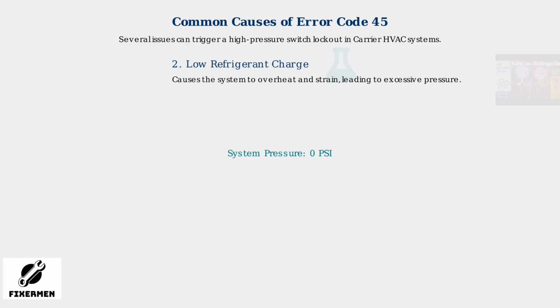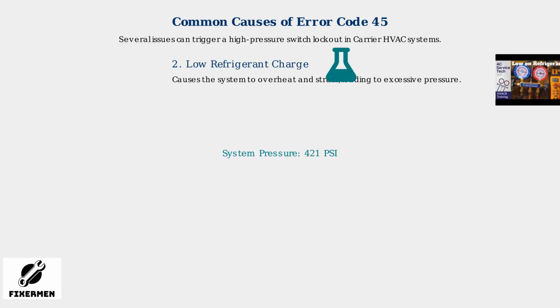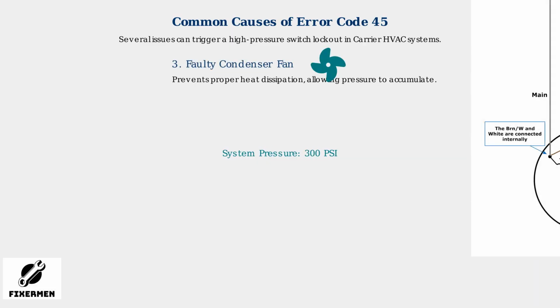The second cause is a low refrigerant charge. When refrigerant levels drop too low, the system cannot cool properly. This causes the compressor and other components to overheat and strain, rapidly building up pressure in the system. The third cause is a faulty condenser fan. The condenser fan helps dissipate heat from the refrigerant. When it fails, heat builds up in the system instead of being released, causing pressure to rise dangerously high.